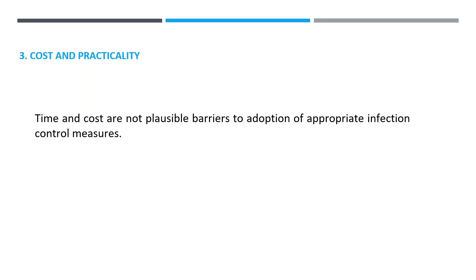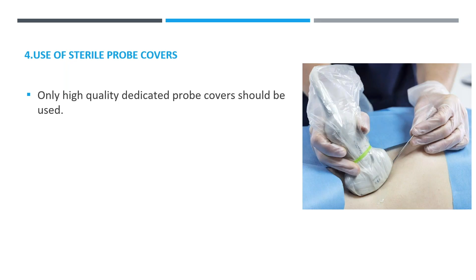What about the use of sterile probe covers? Well, firstly, handmade covers, the use of Tegaderm strips, were never designed for this, and they provide an ineffective barrier and should never be used. Sterile probe covers aren't actually medical devices and are not covered under TGA legislation, so there's no clear definition of what they are. There is good research to show that dedicated probe covers made for the purpose have a very low, though not a no, leak rate, and they also minimize the image degradation that they cause. And so our recommendation is that only high quality dedicated probe covers should be used.